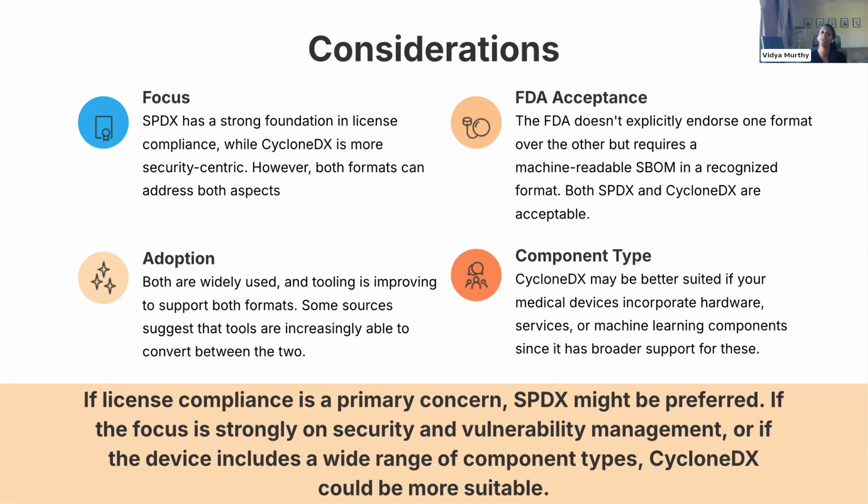Again, is the FDA asking for your hardware to be included in their minimum? No, they are not. There was a lot of debate about including it in the long term, and we're likely going to see some maturation around hardware in the future once the next version of the post-market guidance comes out. In terms of machine learning, the FDA has recently introduced their guidance around AI and LLM management. While they're not explicitly saying we need to see an SBOM for LLMs, I think it's probably expected in the future that some version of that will come down.